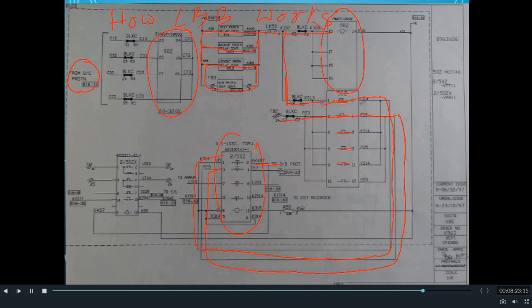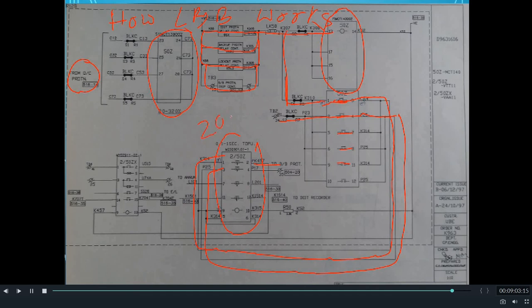Now, the question is why this time delay unit in the LBB relay is used. This delay unit is provided to delay the operation of LBB. That means when both criteria for operation of LBB are fulfilled — that is, when there is current flowing through the LBB relay as well as any of the protection relays actuates — LBB will get initiated. But the operation of LBB will take place only after the time delay unit is actuated. The time delay can be set manually, with a range of 0.1 seconds to 1 second. In general practice, a time delay of 200 ms is set for the LBB relay. Hence, operation of the LBB relay will take place only when both criteria are satisfied and both conditions prolong for more than 200 ms — then only LBB of a particular feeder will actuate.